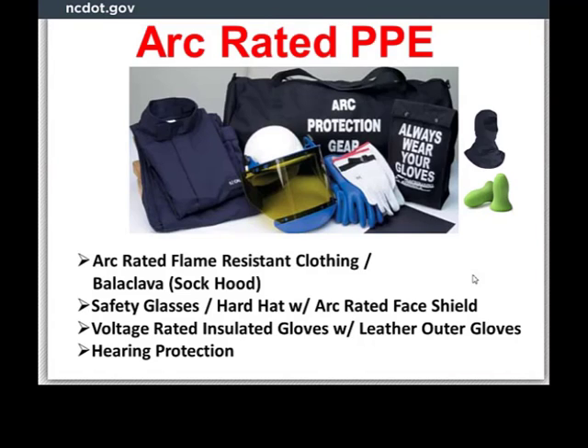Troubleshooting electrical distribution systems in your building. Arc-rated PPE must be worn to protect you from an arc flash for the available incident energy present as indicated on labels attached to the electrical equipment being serviced. PPE must include arc-rated flame-resistant clothing consisting of pants with shirt or coveralls, balaclava, also known as a sock hood, safety glasses, hard hat with arc-rated face shield, voltage-rated insulated gloves with leather outer glove. Hearing protection must also be worn to protect you from the excessive noise levels during the arc flash blast that occurs. Lockout tagout must be used to make the repairs so live electrical work is not performed.